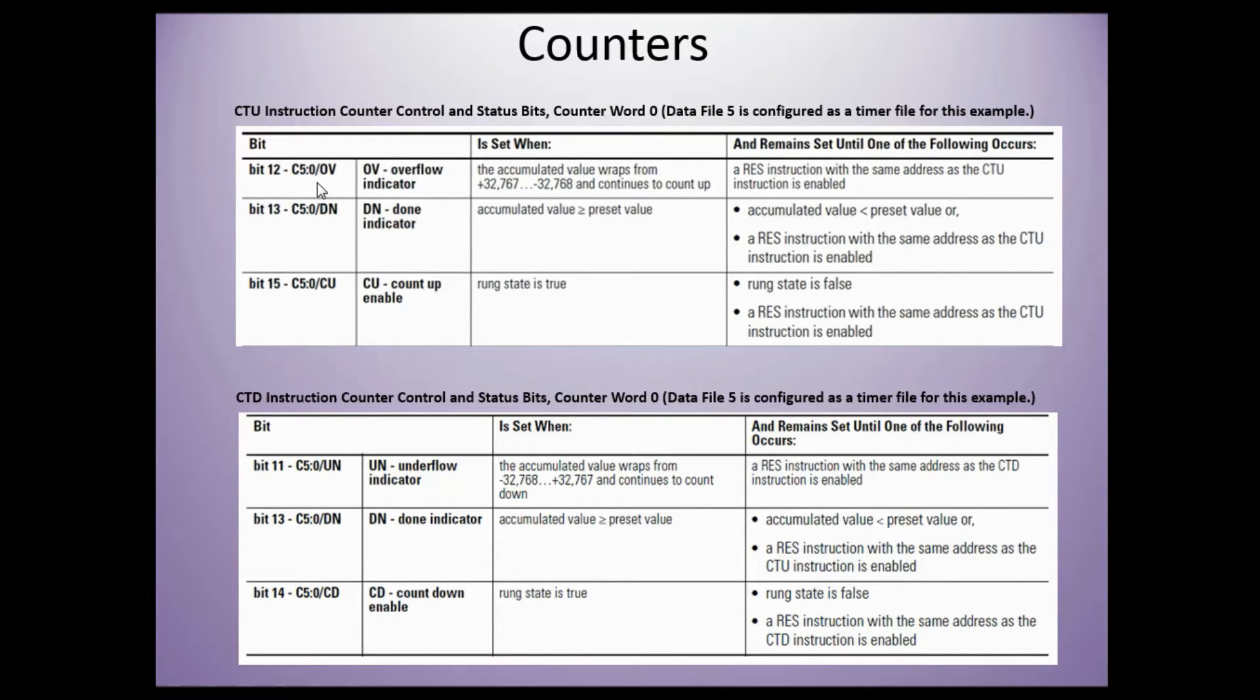With bit 12, the OV bit overflow indicator, the accumulated value wraps from positive 32,767 to negative 32,768 and continues to count up. A reset instruction with the same address as the CTU instruction is needed to reset it. If that OV comes on, it's never going to shut off unless you actually reset the counter, and we're going to show you how to do that when we get into the programming.